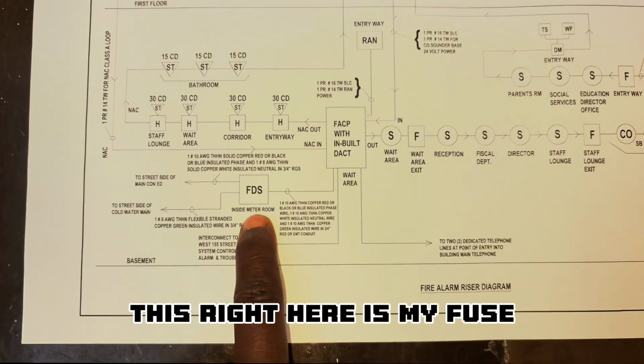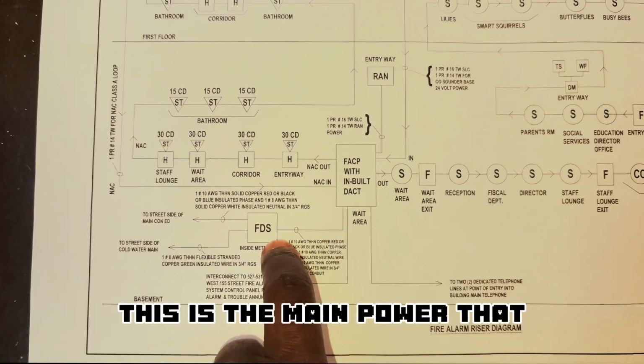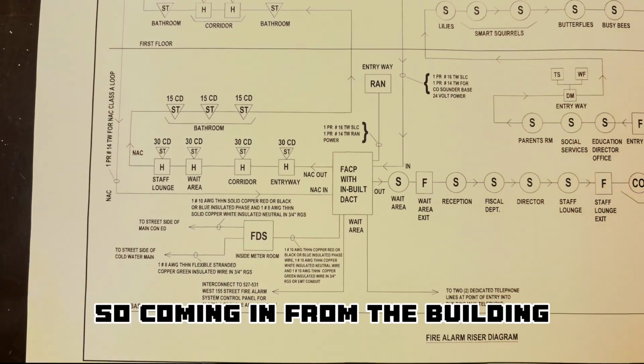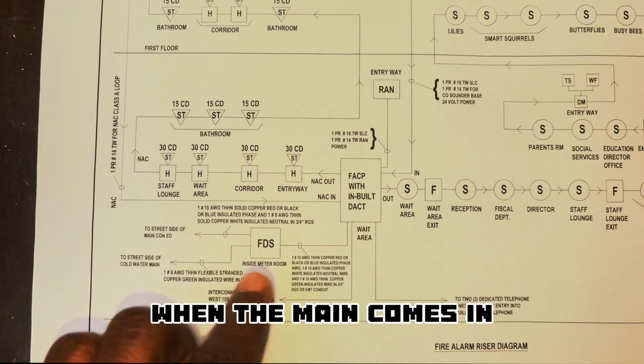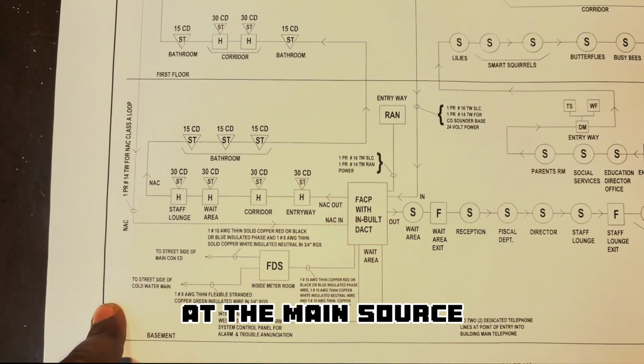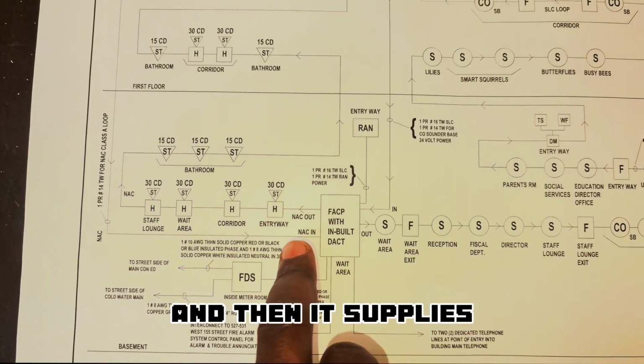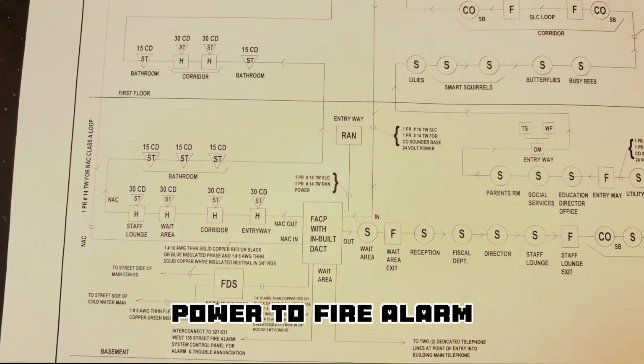This right here is my fused disconnect switch. This is the main power that serves the fire alarm panel. So coming in from the building when the main comes in, this fire alarm panel is tapped at the main source, at the main electrical panel, and then it supplies power to the fire alarm control panel.